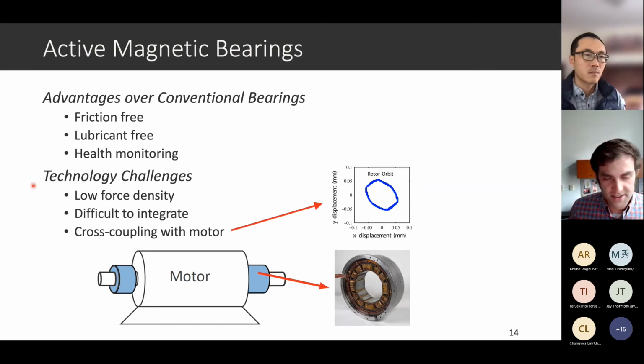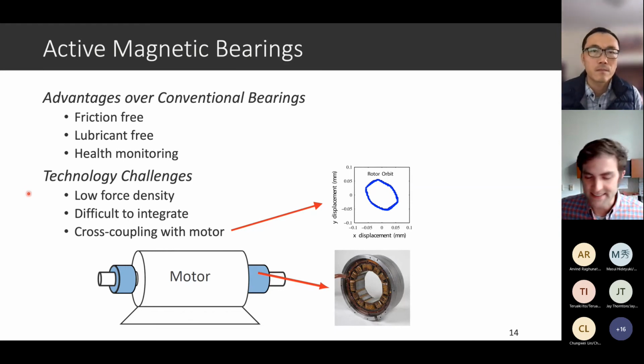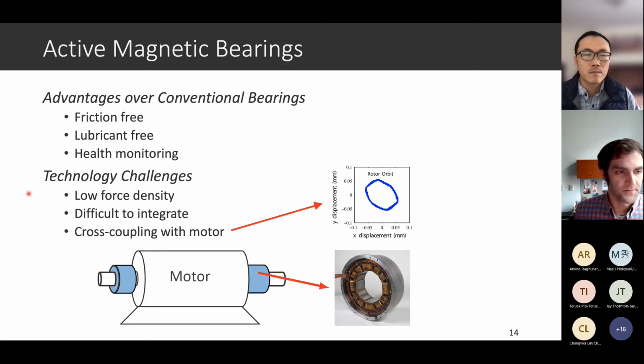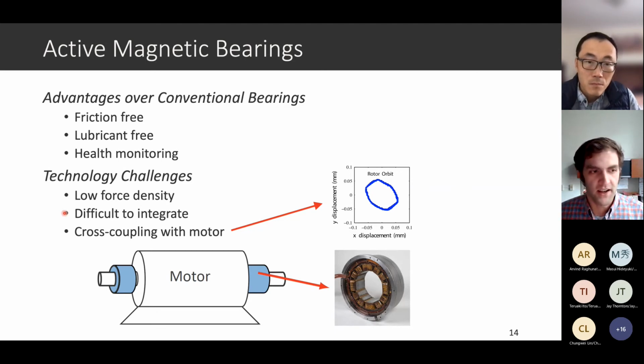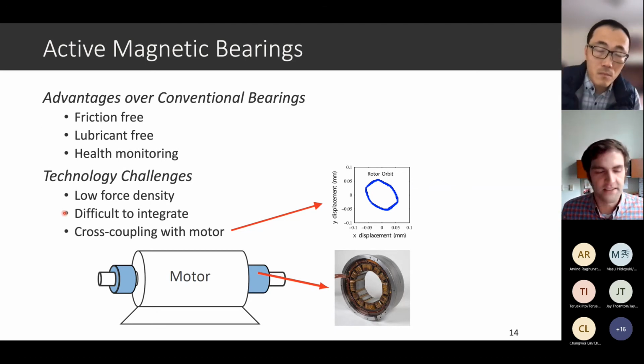But the challenges are very significant with active magnetic bearings. So far, they really only make sense in certain niche applications like very large HVAC systems, in fact, not small ones. What are the challenges? Well, these bearings are big. They have a low force density, especially compared to a ball bearing or a journal bearing. They're difficult to integrate. There are lots of wires that have to be routed. They come with a lot of sensors that have to be very precisely aligned. Everything has got to be aligned and installed just right.